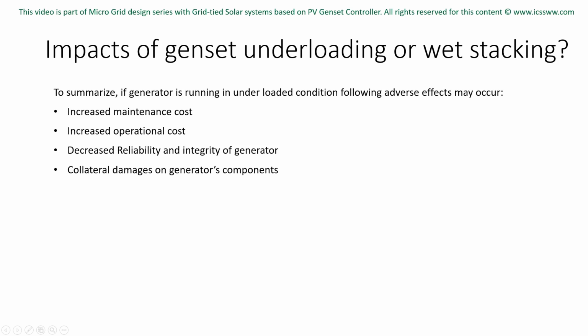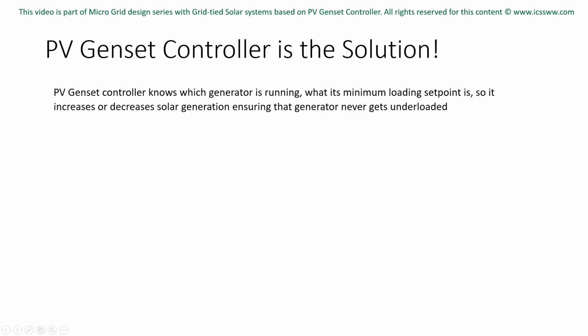To summarize the above mentioned points, if a generator is running in underloaded condition, the following adverse effects may occur: increased maintenance cost, increased operational cost, reliability of the generator decreases, and it can lead to collateral damage to the generator's components. The above damaging occurrences have a cumulative effect on generator sets. First, users are likely to observe unexplained power losses and intermittent poor performance. This is due to the inefficient operation as well as highly accelerated wear on components.